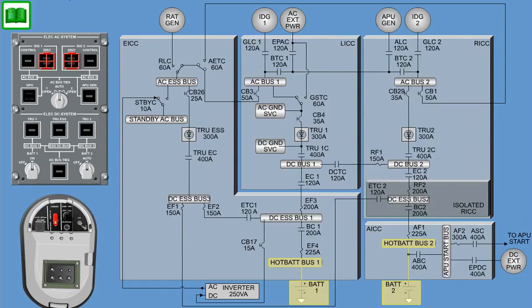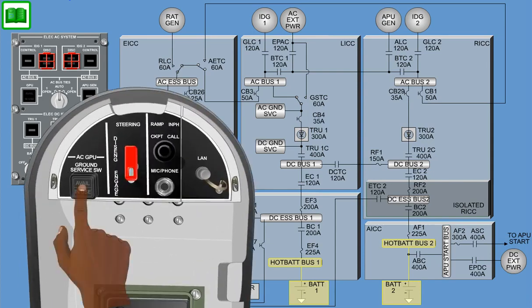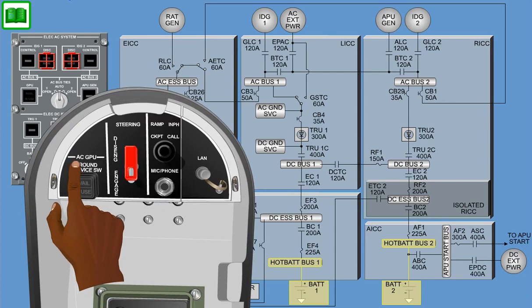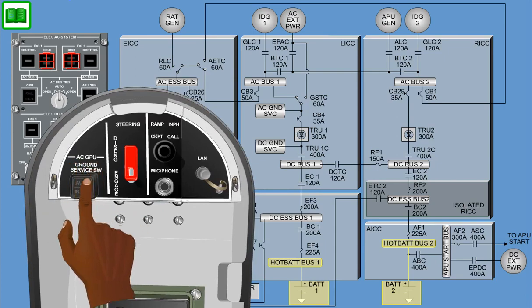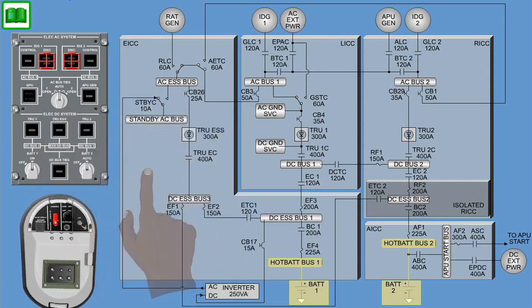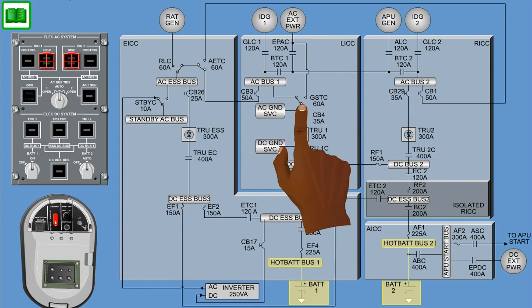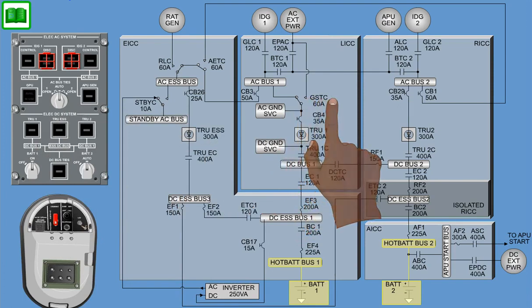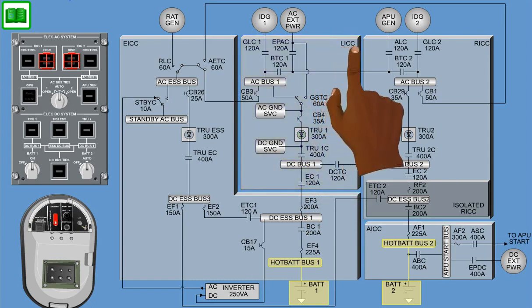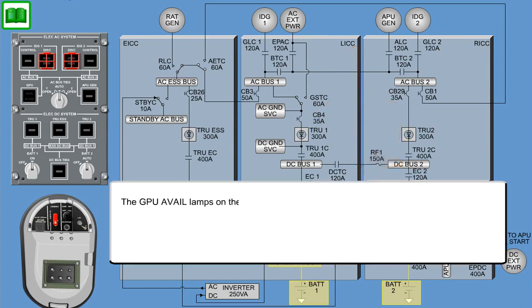A momentary action-type ground service switch is located on the AC external power panel. It is marked as an AC GPU and includes the avail and in-use indicator lights. This ground service switch provides control of the ground service transfer contactor, GSTC, through the external power module, EPM, inside the left integrated control center, LICC. The GPU avail lamps on the cockpit control panel and on the external power panel will illuminate if power quality is acceptable, and the interlock system, pin EF, on the external power plug, is in order.